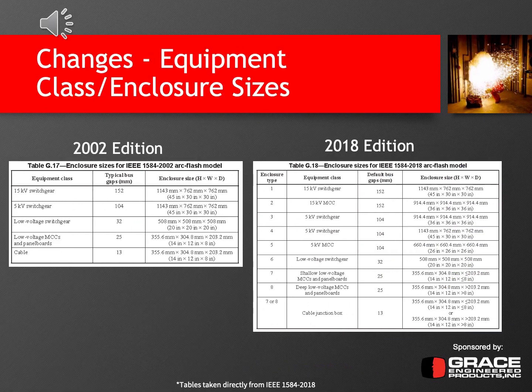One of the other major changes was the equipment class, or the enclosure size. These two tables are both produced in the 2018 edition of IEEE 1584, but as you can tell from their titles, one is relevant from the 2002 edition and the other is the 2018 edition. The 2018 edition has a number of additional enclosures and enclosure sizes. I just wanted to point out that a lot of additional enclosure sizes were taken into account when performing these 1,700 additional tests. Because of that, the empirical data suggests these equations are much more accurate than those in the 2002 edition. This also shows you the different default bus gaps and enclosure sizes based on the equipment class, which is useful information when performing your updated 2018 edition arc flash study.